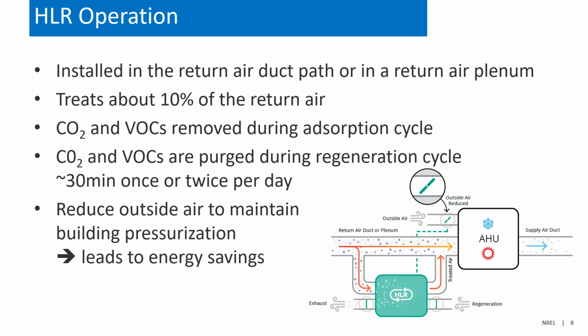All right, so typically what you would do is you would install this in two places, either in the return air duct, as shown in that bottom right-hand picture. And so you treat about 10% of that return air, remove the gaseous contaminants, and then deliver that to the return air duct and then to the building spaces. Or, if you have a large return air plenum, you would just put that HLR right in the return air plenum and treat the air right in the plenum itself.